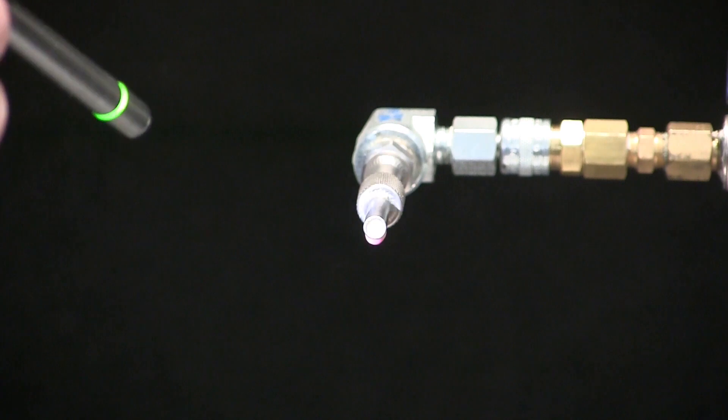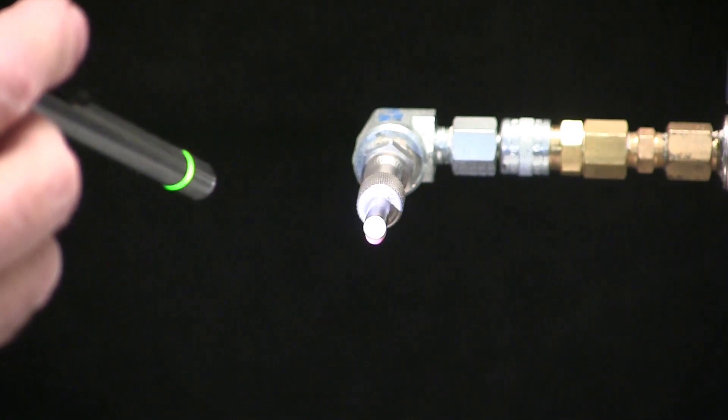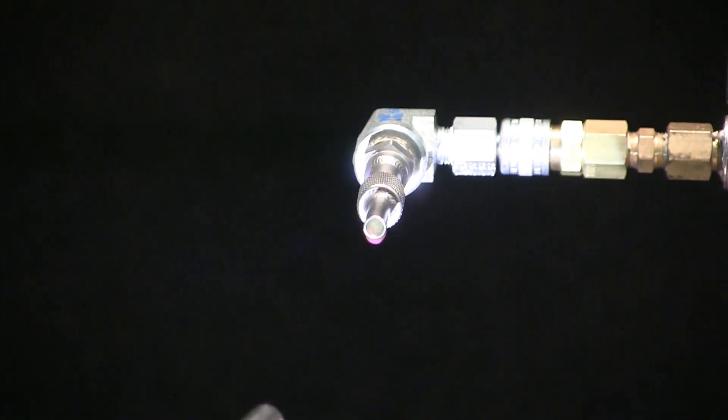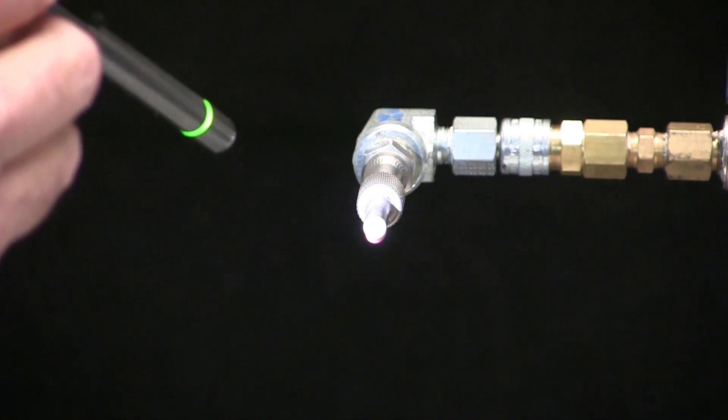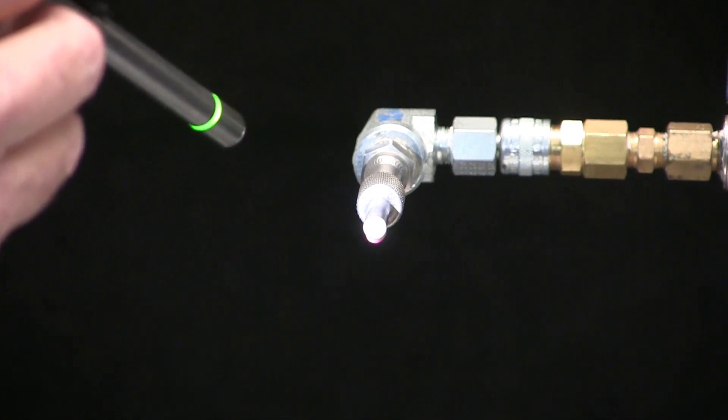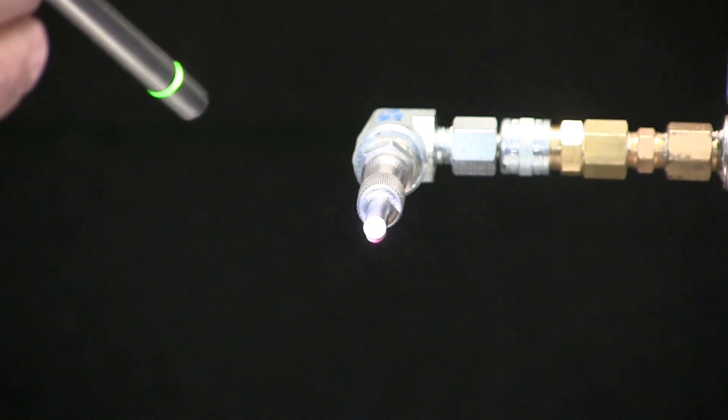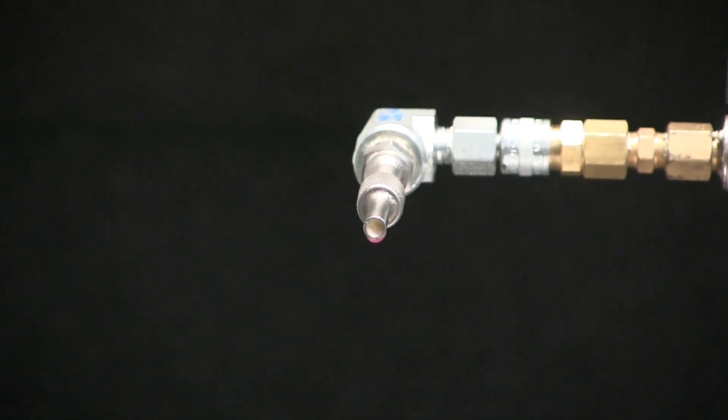It's starting to change color in the capillary here. We can see that the color change is changing to yellow. We can see down here it's more pinkish. So it's definitely changed the color indicating that that's a leak. The Bullseye foam can definitely identify an air conditioning leak.